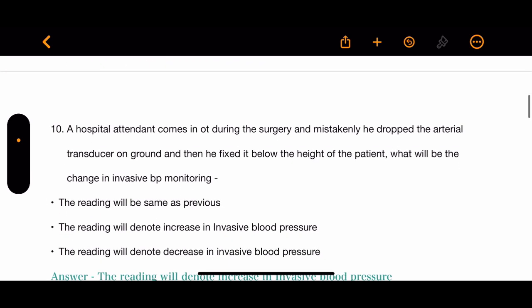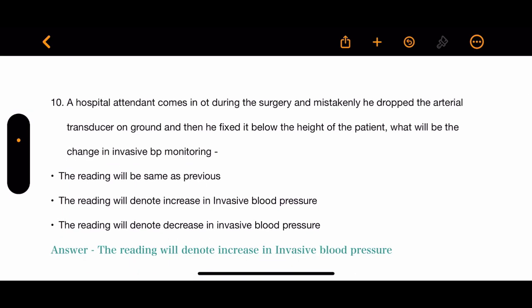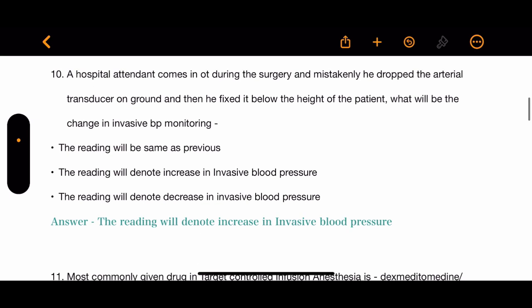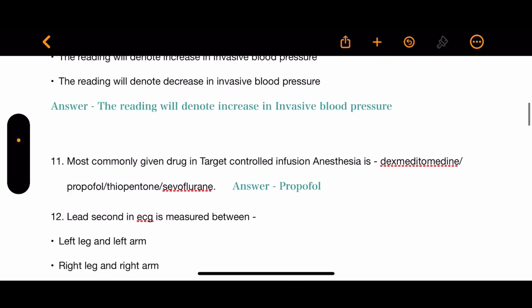Question 10: A hospital attendant comes into the OT during surgery and mistakenly drops the arterial transducer on the ground, then fixes it below the height of the patient. What will be the change in invasive blood pressure monitoring? The correct answer is the reading will denote an increase in invasive blood pressure.